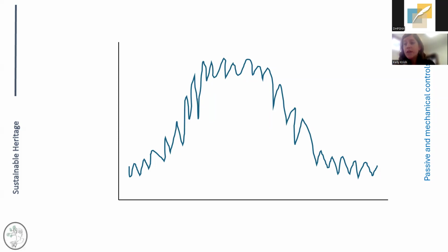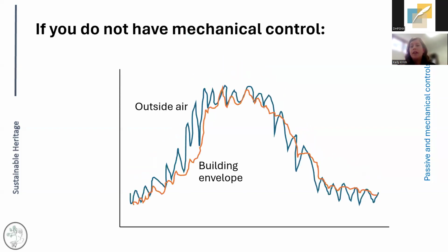For places that see fewer seasonal swings, you certainly would see less of an extreme in terms of your outside dew point, but it's just a good place to start. If you don't have mechanical control and you have your outside data and you bring up data from within your building in a space, you will see something that looks similar to your outside air, but essentially a buffered version. So it's not going to reach the same highs and lows as fast. It maybe won't even reach the same extremes if they're not maintained.